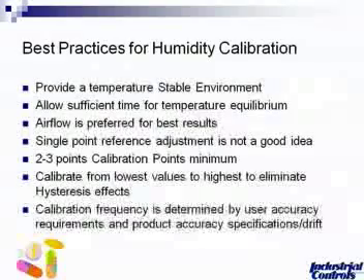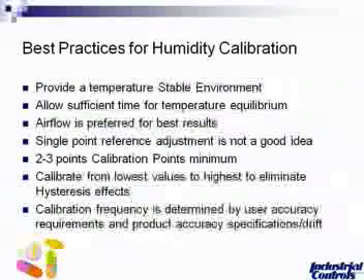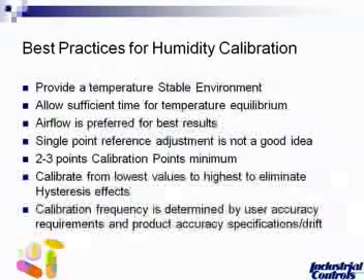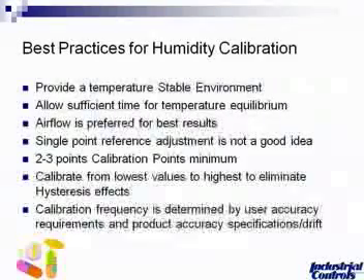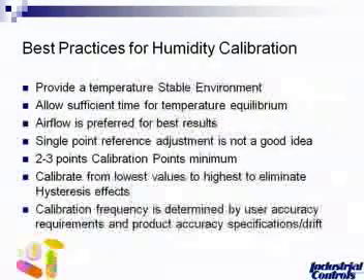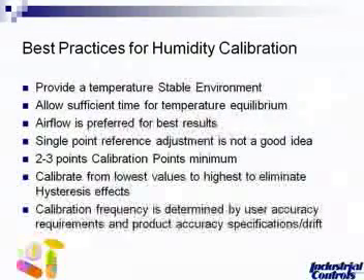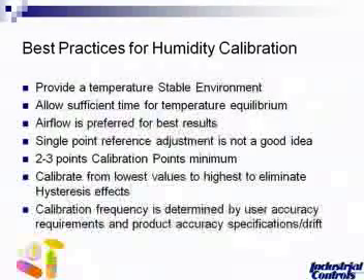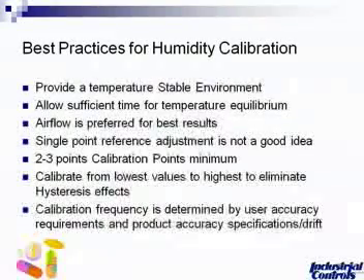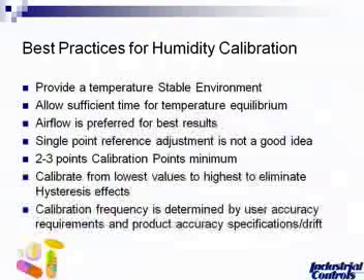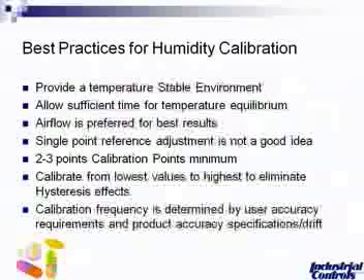Some of the best practices for humidity calibration: you want to make sure that your temperature is stable, since relative humidity is a function of temperature. Air flow is preferred for the best results because you're going to get faster response on both temperature and humidity. A lot of customers do single-point calibrations, but that's not truly a calibration. A single-point reference adjustment is okay if your only critical point is, say, 50% RH — but what you're doing is adjusting the whole curve so at 50% you're accurate but you may no longer be accurate at the high or low ends. You definitely want to try for a better calibration with two to three points minimum. It's a good idea to calibrate from the lowest values to the highest values to eliminate any hysteresis effects.